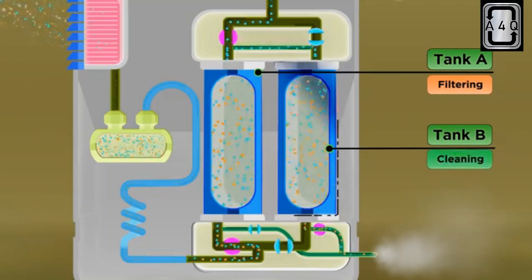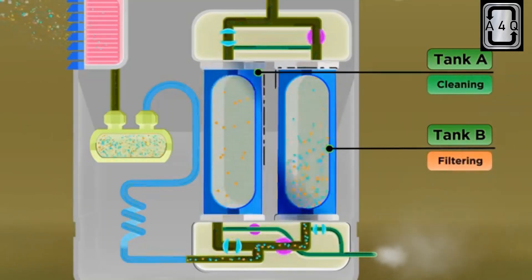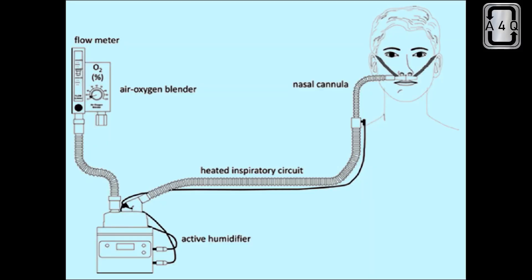This process of switching the sieve beds is known as pressure swing adsorption. The output of oxygen is then controlled using a flow meter where the flow can be set manually in liters per minute.